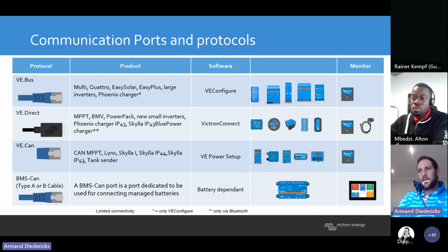This BMS CAN cable doesn't work with Color Control, it only works with your Cerbo GX. If you do have a Color Control connected, you need to use the VE.CAN to communicate to the battery, then your protocol will also just change. If you have a VE.CAN and/or Cerbo or Color Control, and you have an MPPT and a battery, and you connect the battery to VE.CAN, I suggest that you use the VE.Direct cable to communicate to the MPPT. Otherwise, you're going to get confusion. They in any way don't work on the same cable.